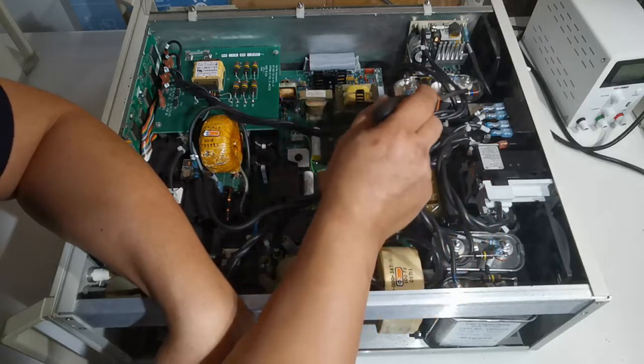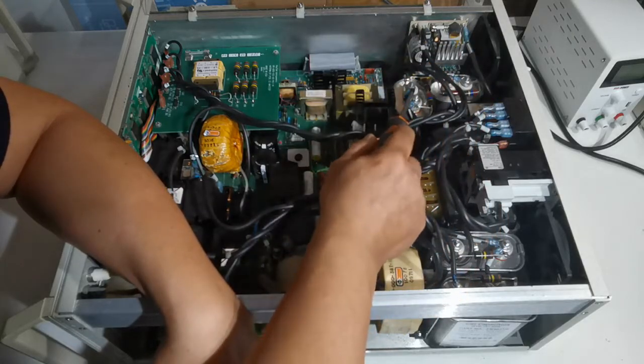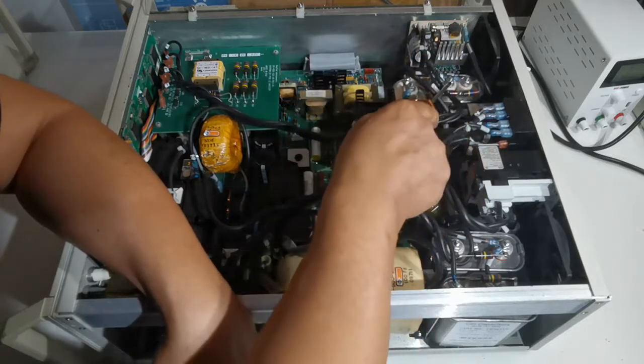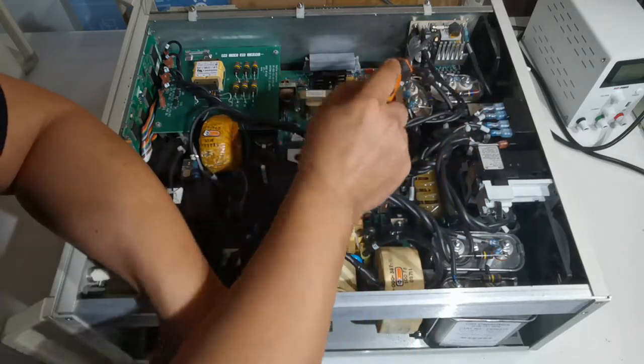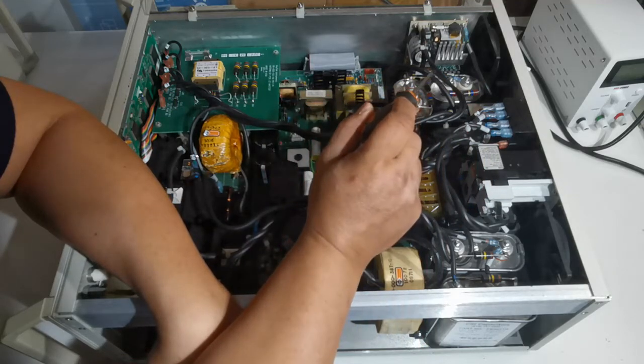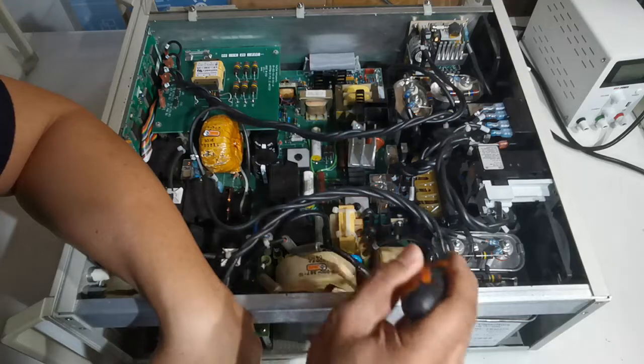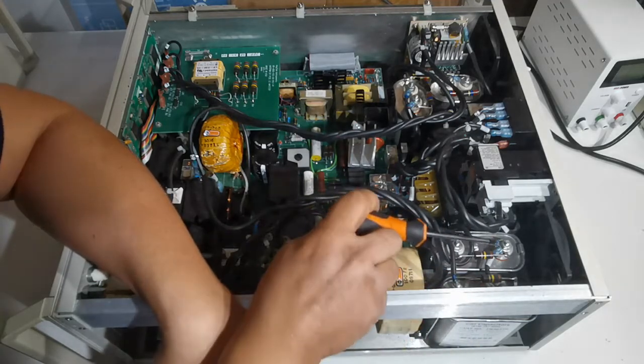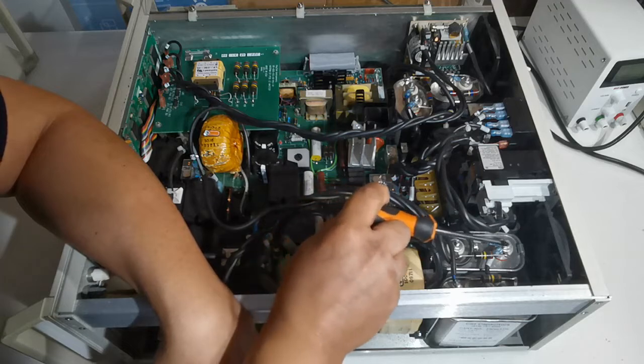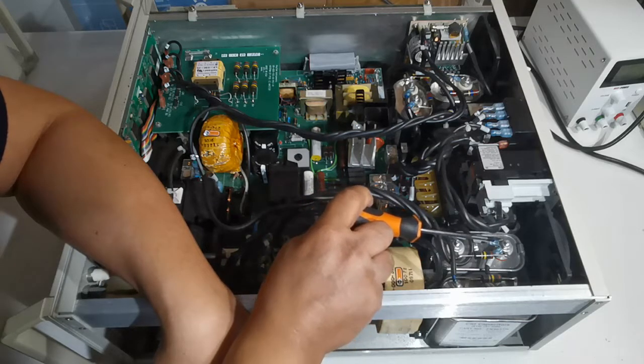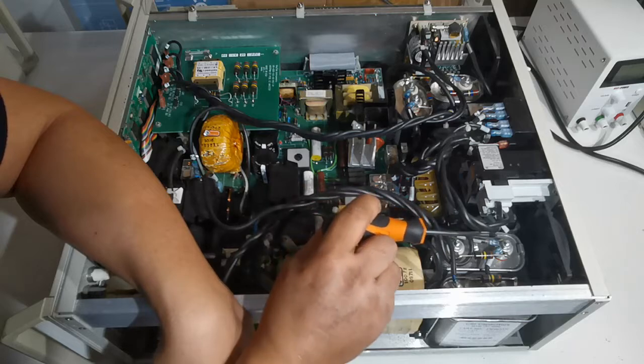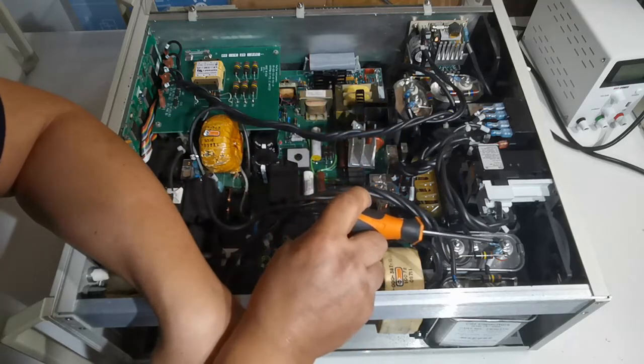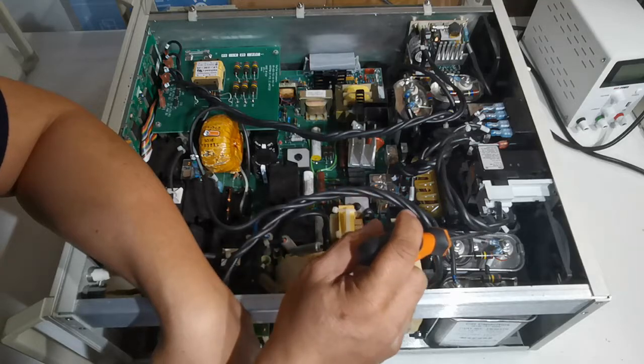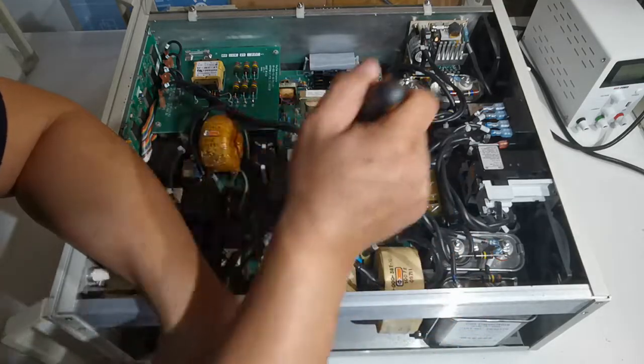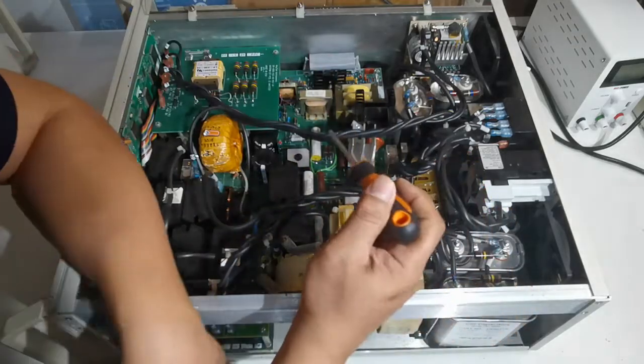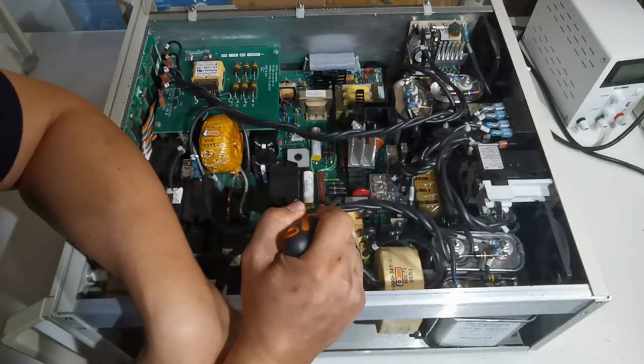On the surge, these two here are the big high voltage capacitors, 5 microfarad capacitors. This is the charging system. This is the charge for the high voltage. And these two capacitors here, which are 10 microfarad 2 kV, are the discharge capacitors, or the shaping capacitors. This will shape the waveform of the surge to make it a 50 microsecond waveform. In conjunction with the other resistor underneath, we will pull this board apart, and I'll show you what's inside behind this board.